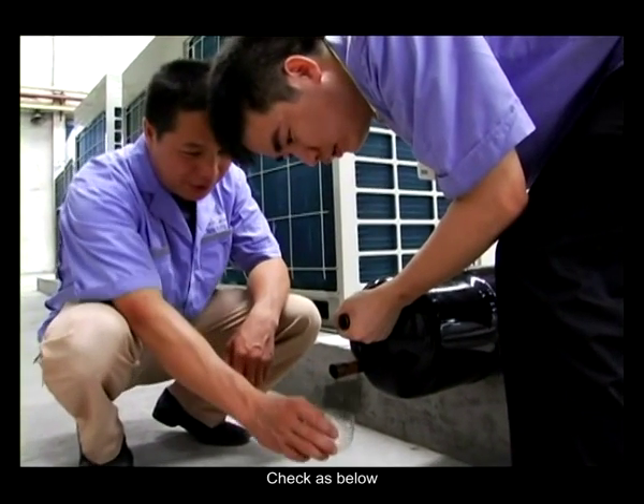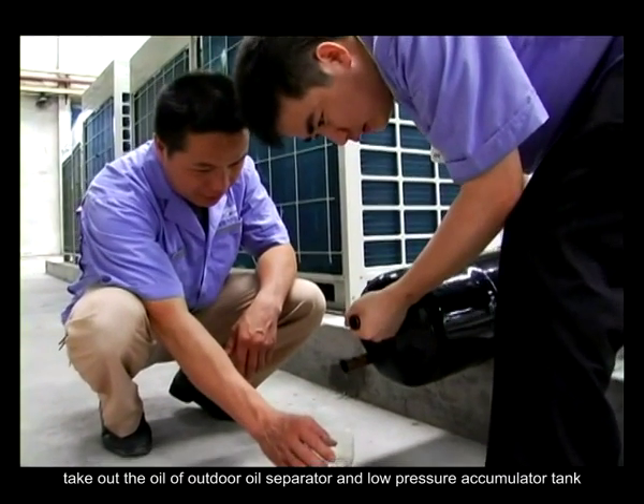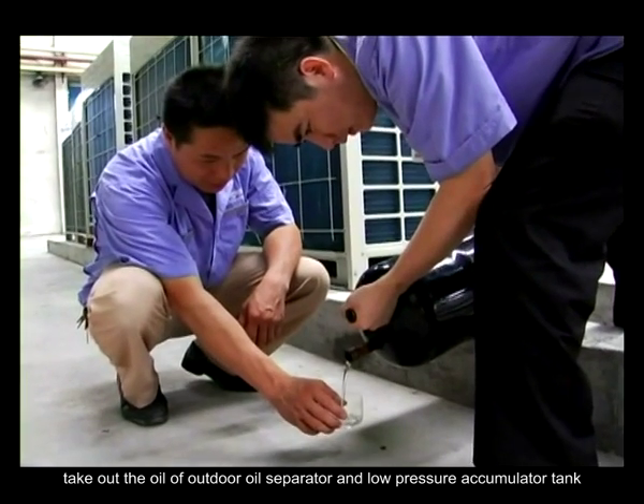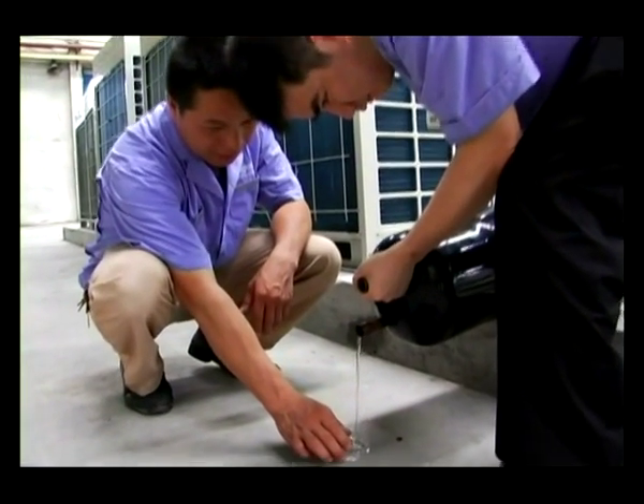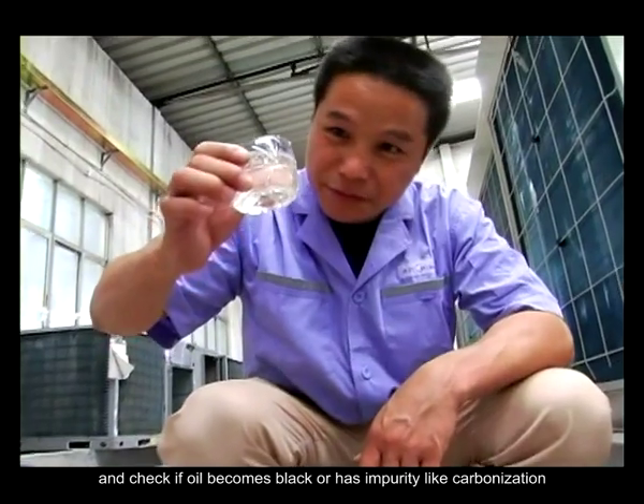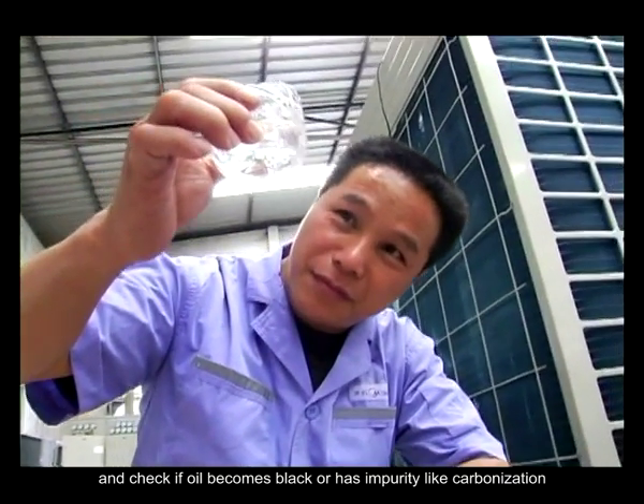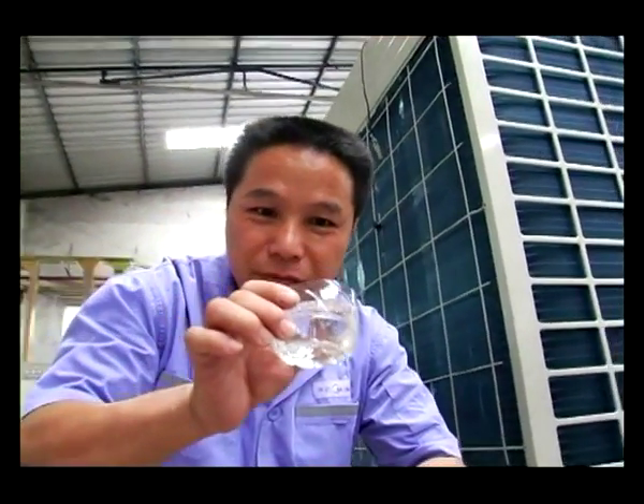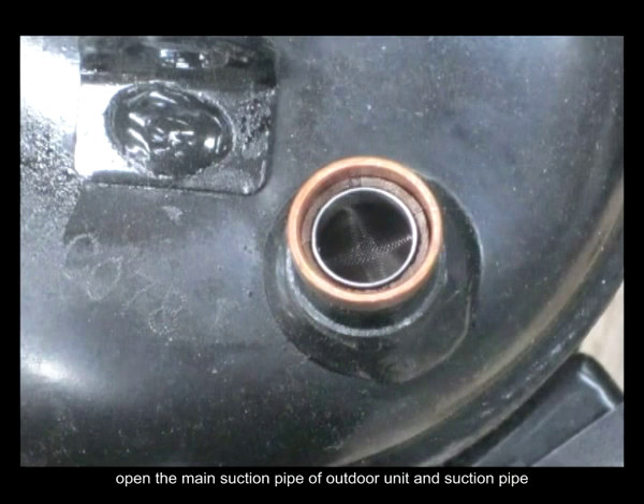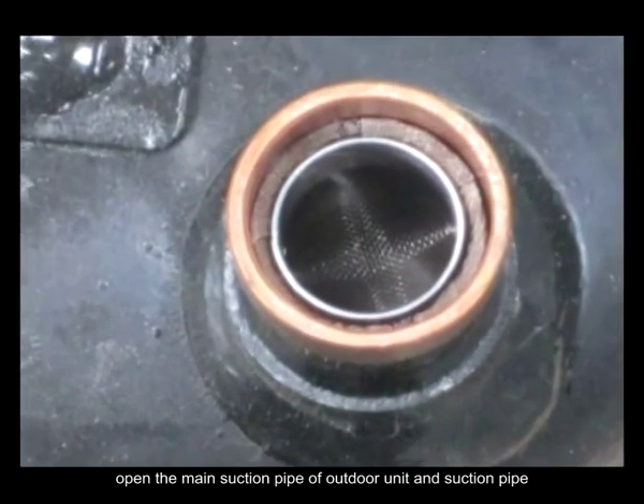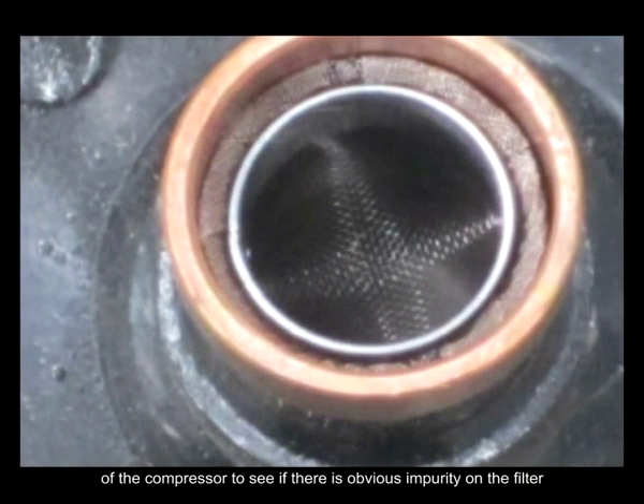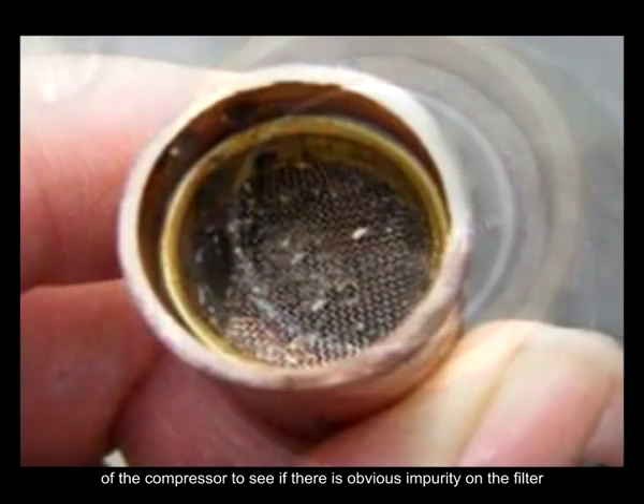Check as below. Take out the oil of the outdoor oil separator and low pressure accumulator tank and check if the oil has become black or has impurity like carbonization. Open the main suction pipe of the outdoor unit and the suction pipe of the compressor to see if there is obvious impurity on the filter.